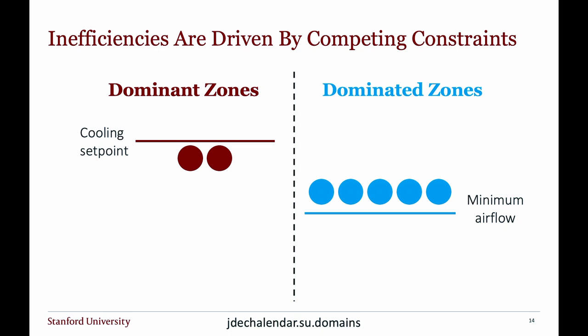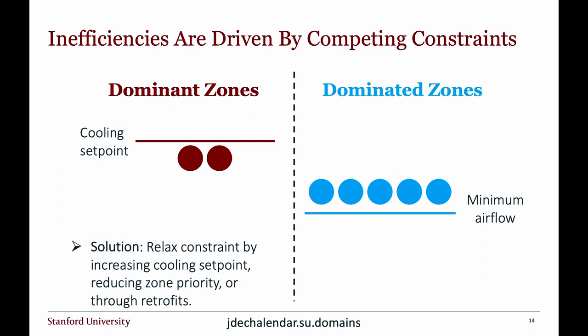So what's the solution if you could find these zones? For a dominant zone, you could relax that constraint by increasing the cooling set point, or if you don't need it, reduce that zone's priority. Those are cheap fixes if the system just wasn't set up right, or more expensive is a retrofit where you augment cooling capacity to that zone if you really need it.